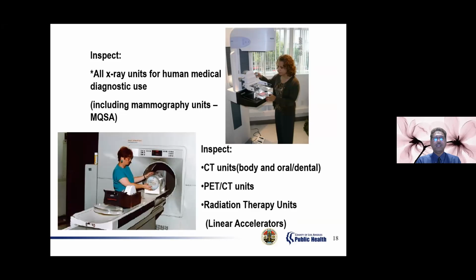We inspect all X-ray units for medical and medical diagnostic use, including mammo units. Inspect CT units, body and oral dental. PET CT units, radiation therapy units, linear accelerators. Just to mention, radiation therapy units. With this type of units, when we inspect these facilities with therapy units, a lot of it is QA/QC material. We don't have the means to really inspect the machine itself, but we do a lot of scatter measurements around the vault or the room of a therapy unit, make sure that the shielding or the vault is intact. There's no scatter radiation coming out of any areas of the room when it's in operation. So a lot of that is basically bookkeeping. There's a lot of bookkeeping on radiation therapy.